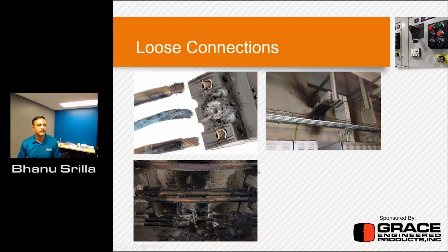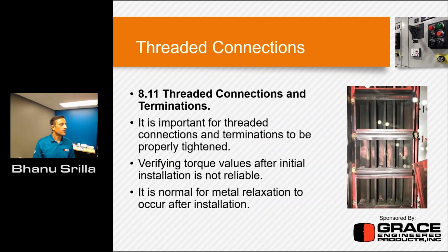The point I'm trying to make here is the loose connections are one of the major things when it comes to electrical flashovers or the arc faults and such, right? So the degradation over time will lead to this kind of scenarios, which could be completely preventable. So if you look at the threaded connections on chapter 811 from NFPA 70B, it's important for threaded connections to be properly tightened. So tightening the connections brings 2 questions: are you tightening this to the proper torque or not? Are you just over torquing or under torquing, right?